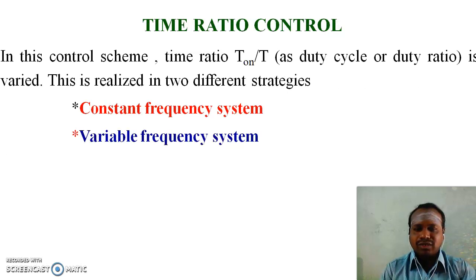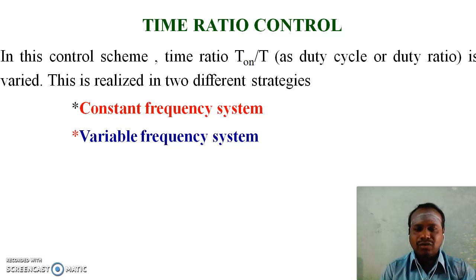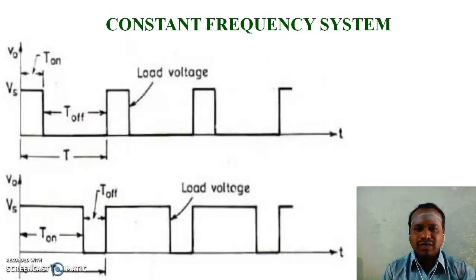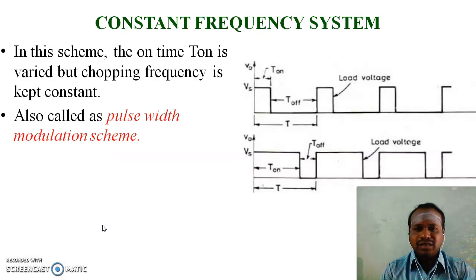In time ratio control, the time ratio — that is, Ton by T, also known as duty cycle or duty ratio — is varied. This is realized in two different strategies: constant frequency system and variable frequency system. In the constant frequency system, Ton is varied but T is kept constant. The on time, Ton, is varied but chopping frequency is kept constant. This constant frequency system is also known as pulse width modulation, because the pulse width, that is the on period, is varied.